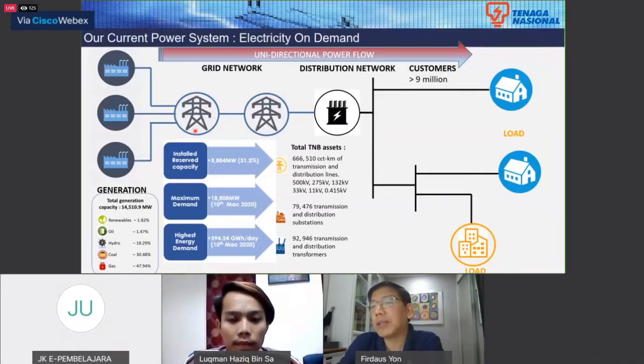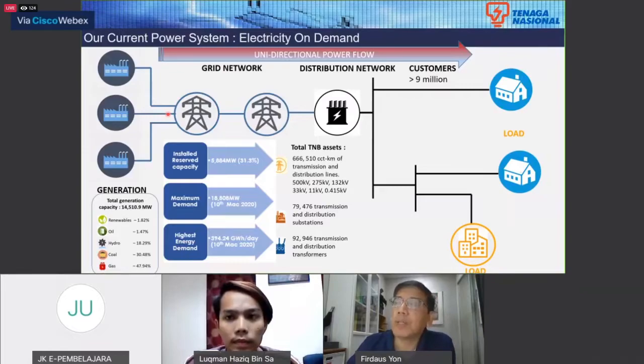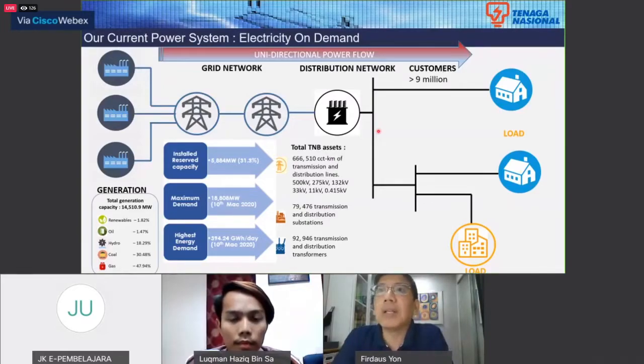So basically, we generate electricity. The generators will pump out power at a voltage of about 11 kV or possibly 33 kV, so it's low voltage. We have step-up transformers that step it up to either 500, 275, or 132 kV. Typically it's either 500 or 275 nowadays; 132 kV transmission is of the older generation. We transmit it all over West Malaysia until we reach, by stepping down, the distribution levels. Distribution level voltages are 33 kV, 11 kV, and finally to the substation in your housing area it will be about 415 volts.